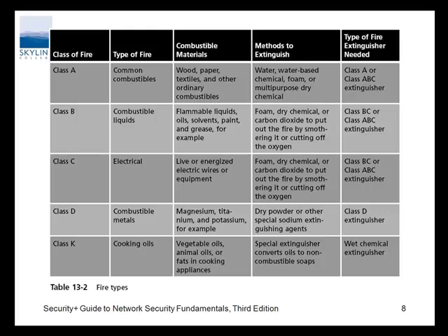And also, even if you had an electrical switchboard, you probably wouldn't want to use that. CO2 is generally considered the best agent. CO2, you have to remember, is very dangerous to human life. You want to wear an oxygen mask. Well, Matt, you're going to have more than a mask. You're going to have an oxygen supply of some sort, a tank of some kind, or an emergency breathing device.